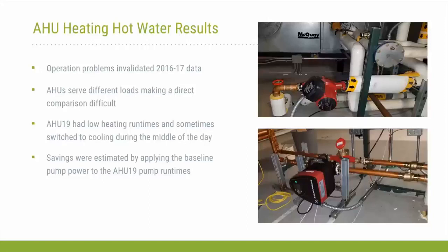It was serving an internal zone within the building, and so it would essentially turn on for a couple hours in the morning to heat the zone up. Then the zone would switch over to cooling mode, and the pump would turn off all day, and then it would run for a couple hours at night. So it was a challenging demonstration from that perspective, because we had a number of changes that happened as we were going along here, but I think there are definitely good lessons learned for future projects. So the way we estimated the savings was, since air handling unit 17 runs at a constant power while operating, we compared its energy usage to air handler 19. Next slide.